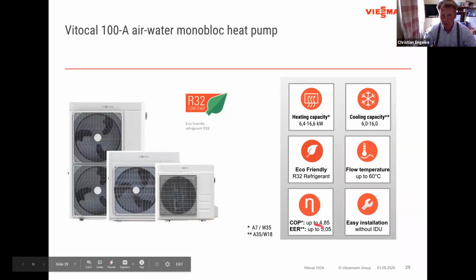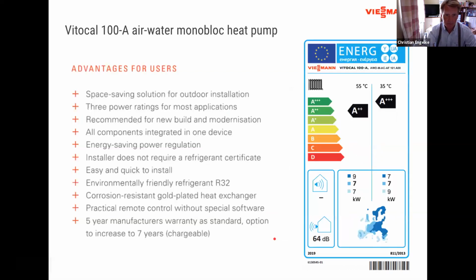Important from the efficiency point of view, which I come to in a minute, is that we need to understand what temperature operations we are talking about. I've mentioned that one last Monday. So A7 stands for an outside temperature of 7 degrees, and W is the water temperature, which is the supply temperature to the heating circuit, of 35. And the cooling output is defined at an outside temperature of 35, water temperature of 18. So just to refresh these definitions there.